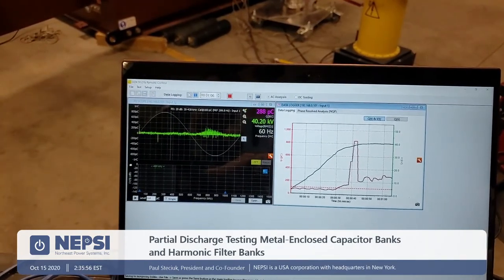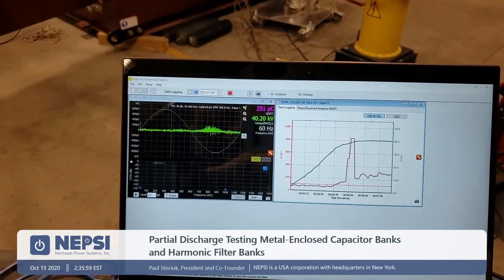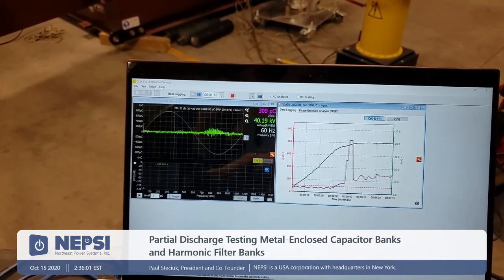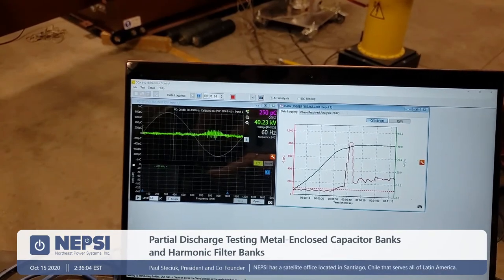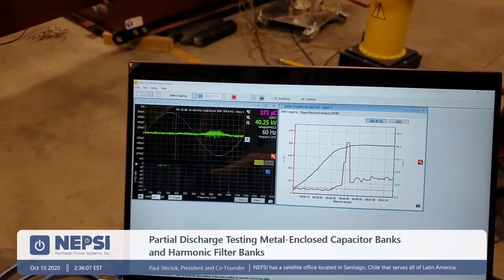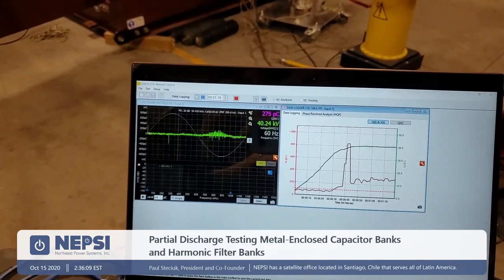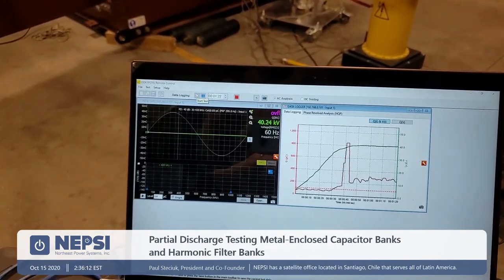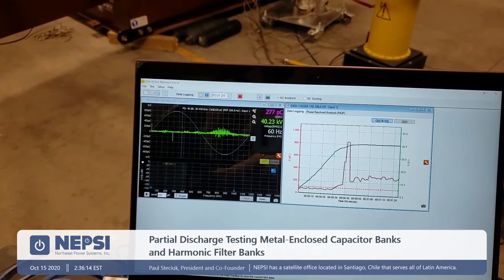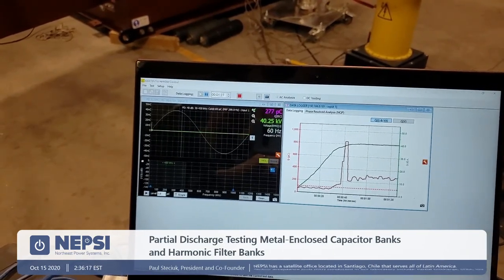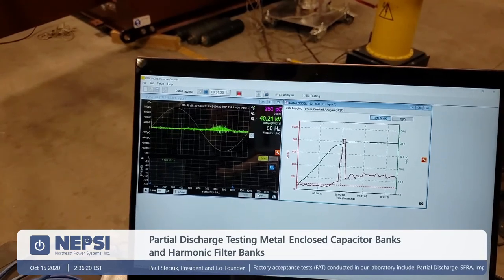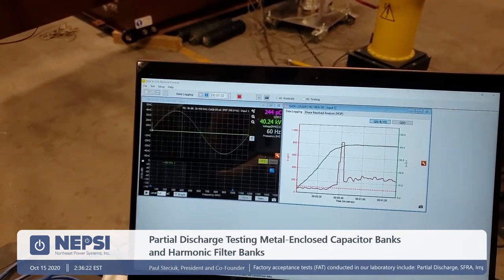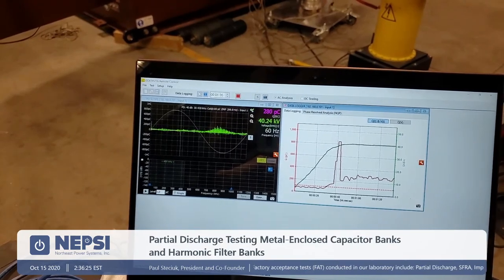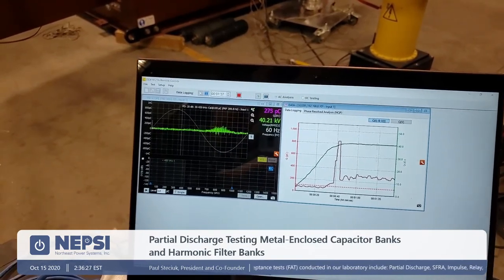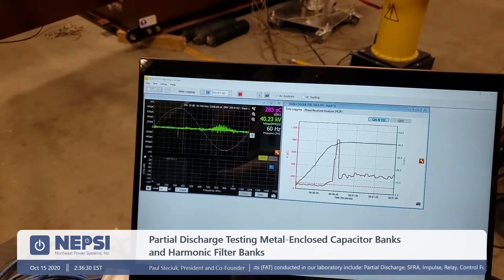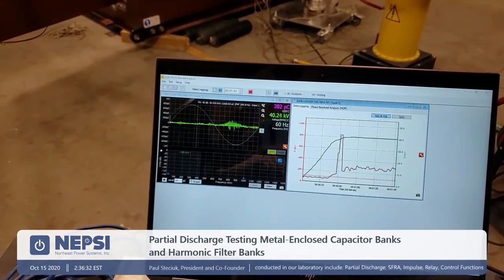Okay, so we will hold it here. How long do you hold it here for? If we go into inception, we can come out any time. Sometimes it may take a little bit to get into it, but we've been finding that normally when we get to that half, we pretty much go into it right around then. Okay. So now Pete's going to start dropping the voltage, and the standard that we're following here dictates that at 26.5 kV we must be at or below 100 picocoulombs, and that would be considered a test that has passed. After 2 minutes. We have up to 2 minutes.